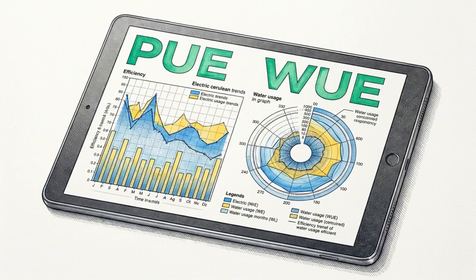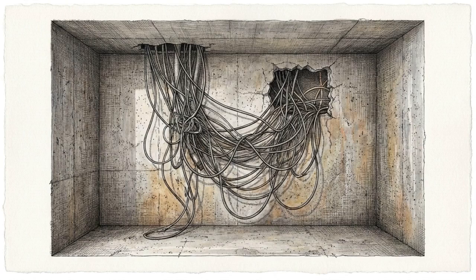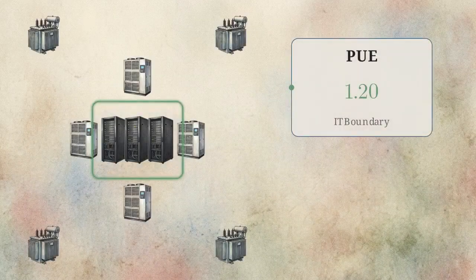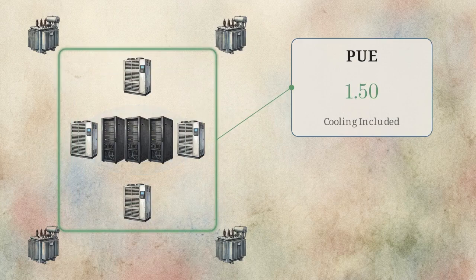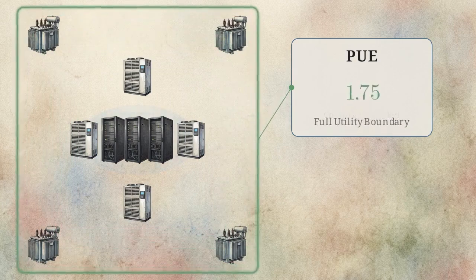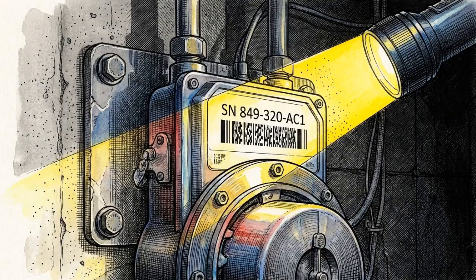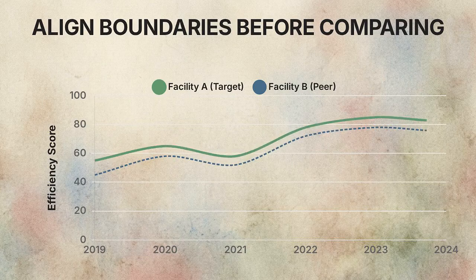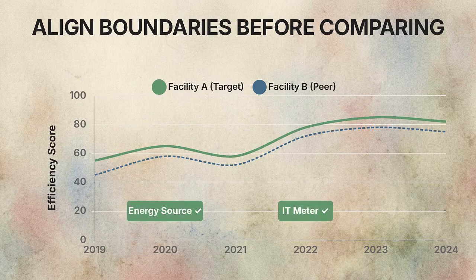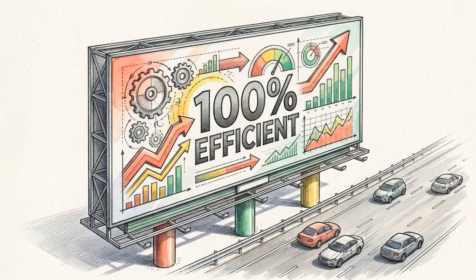This traceability framework dictates the validity of a facility's most publicized efficiency metrics, like power usage effectiveness and water usage effectiveness. The mathematics of these metrics are entirely irrelevant if the physical placement of the meters remains undefined. Watch what happens to the output on this floor plan if the defined boundary of the utility meter expands and contracts to include or exclude specific power losses. The resulting PUE calculation wildly fluctuates, even though the underlying IT load has not changed at all. You cannot evaluate performance accurately without verifying the physical source of the data. Never compare metrics across sites unless the energy source, IT meter location, and water scope are perfectly aligned. A metric without a verified boundary is just marketing.